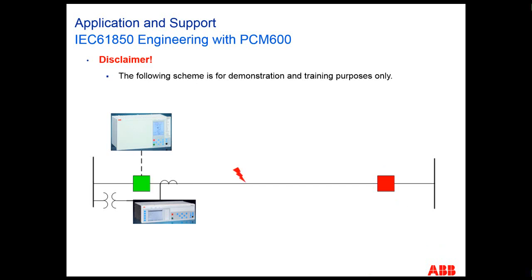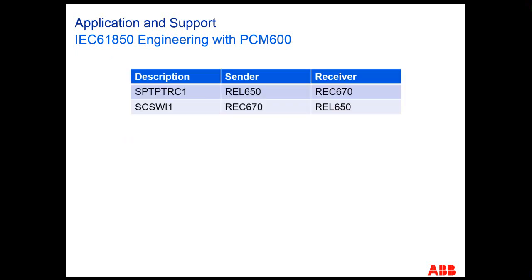On the event of a fault, the tripping signal is going to be published and this information received by the REC670 relay. The REC670 relay is in charge of publishing the circuit breaker position; therefore, it is going to change from a circuit breaker position closed to an open position. To summarize, the SPTPTRC1 is going to be published by the REL650 and received by the REC670. The second, breaker position SCSWI1, is going to be published by the REC670 and received by the REL650.